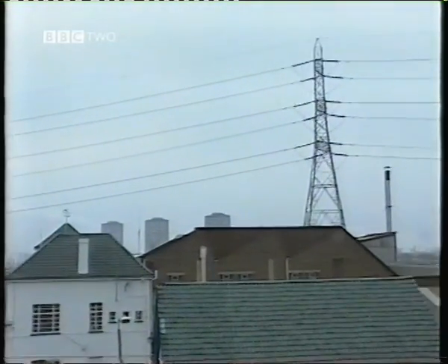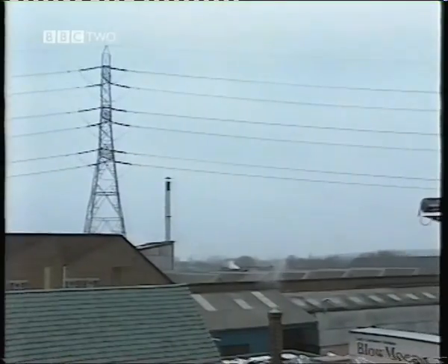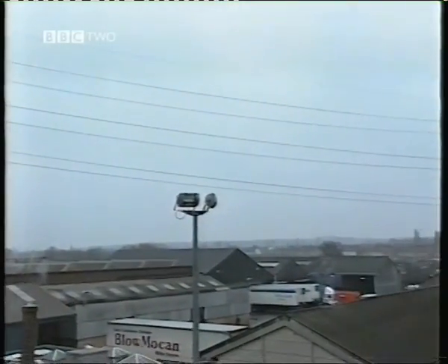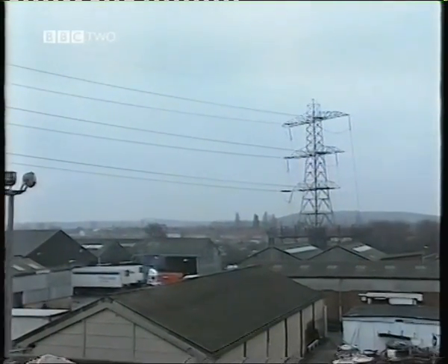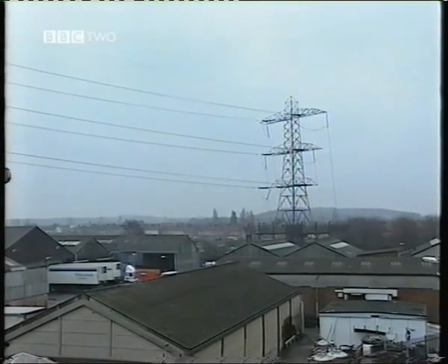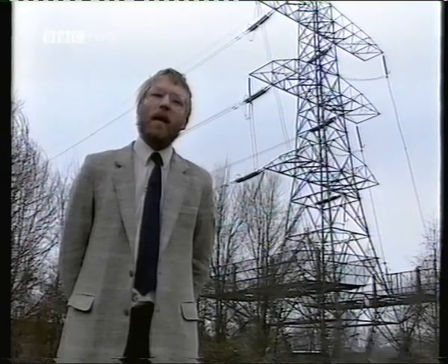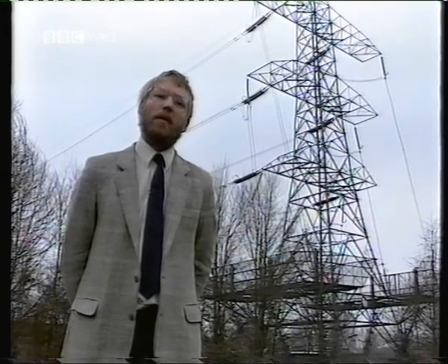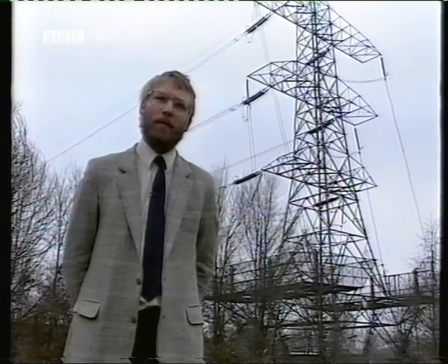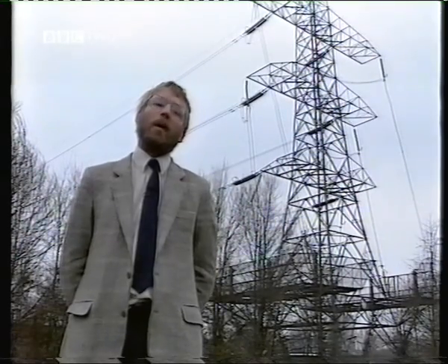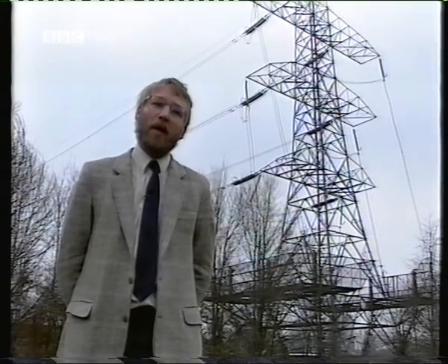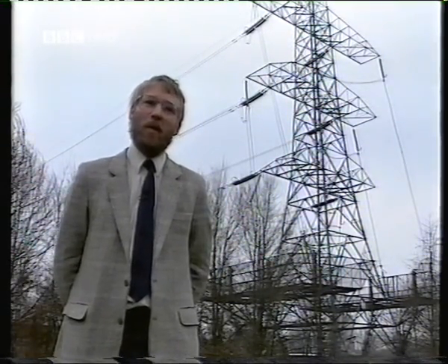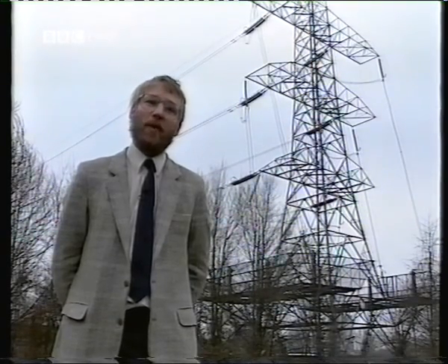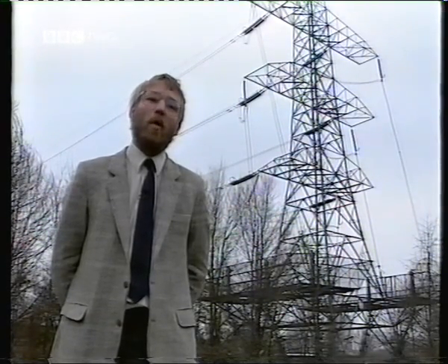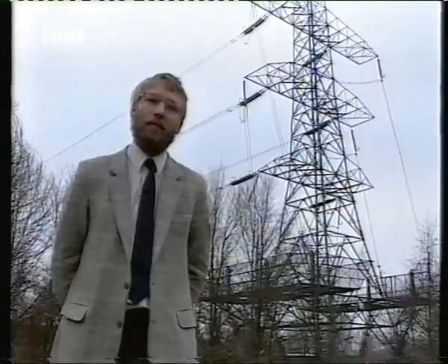It's easy to see examples of these overhead lines, but they're just one solution to the grid's supply needs. The line hasn't come to an end here, it's just come to a built-up area, and the cables have to go underground. So what do you think the materials problems are? Well, we can't use air as the insulator anymore, and we've got to allow for the fact that the cable gets warm when it's carrying current.